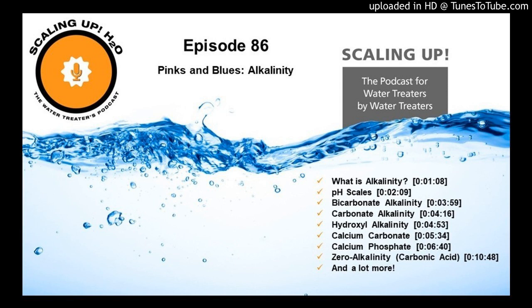And the reason that we have OH alkalinity in the boiler, and I'm not going to get too deep into this, but we need to make hydroxyapatite and not calcium phosphate. Calcium phosphate, I remember when I was younger, my father took a sample of calcium phosphate and he threw it against a concrete wall and it dented the concrete wall. Folks, this stuff is really hard to get rid of. It can be created very quickly, but it takes forever to get rid of it.